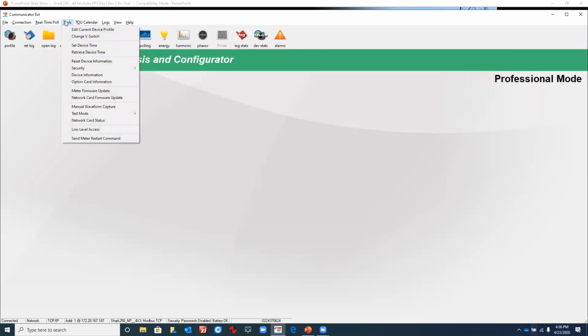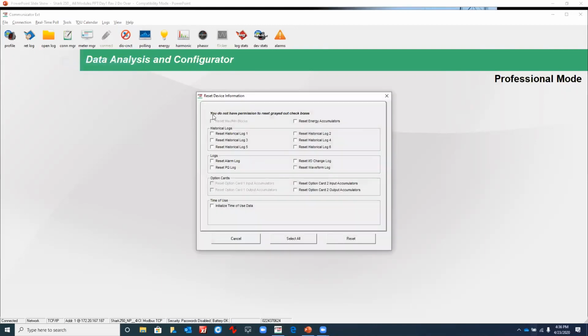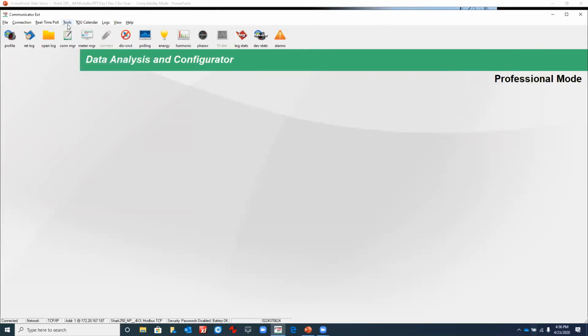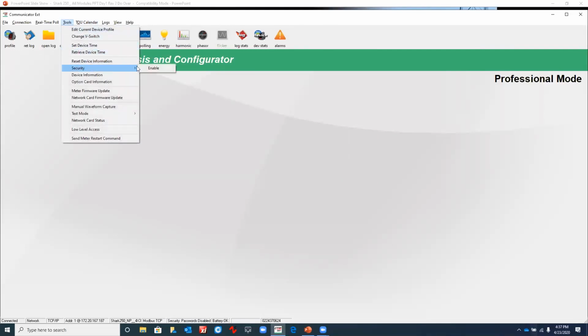So let's take a look at the tools menu. On the tools screen, we have edit current device profile, the change V switch, which we discussed briefly earlier. What other things can we do here? We can set the device time, we can retrieve device time, we can reset the meter information. That is all the information, the log information. If you want to clear everything out, which we don't want to, it can be very dangerous. For security, you can enable security, which we'll talk a little bit about tomorrow. Then the device information, the option card, meter firmware updates, you can choose from here. So if you decided you want to update a firmware, this is what you would select.